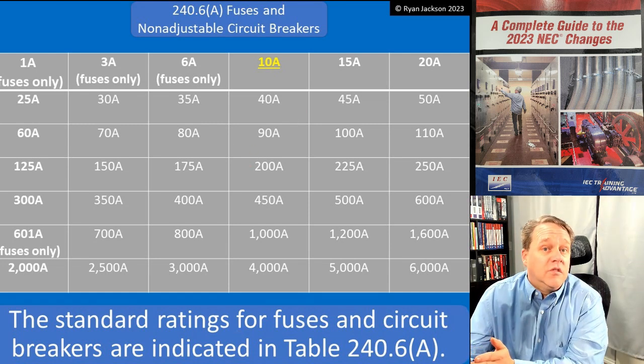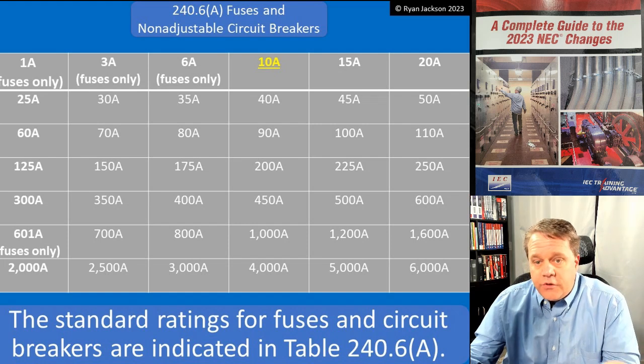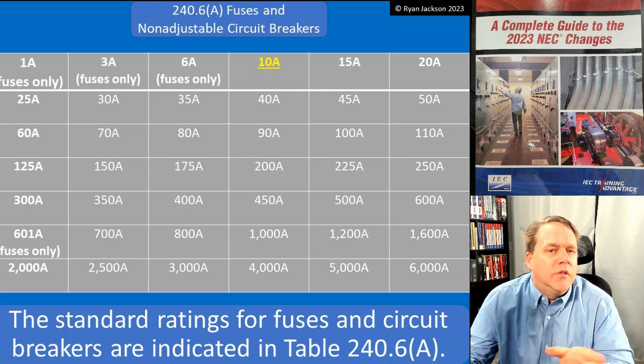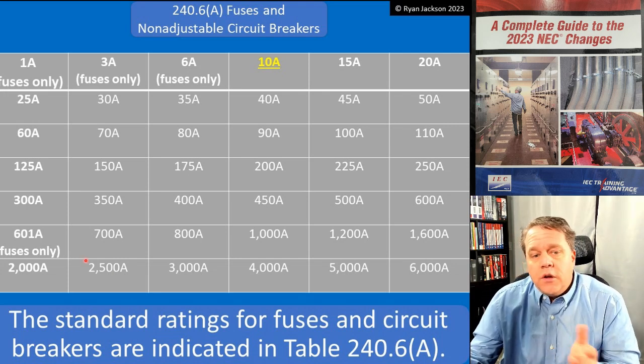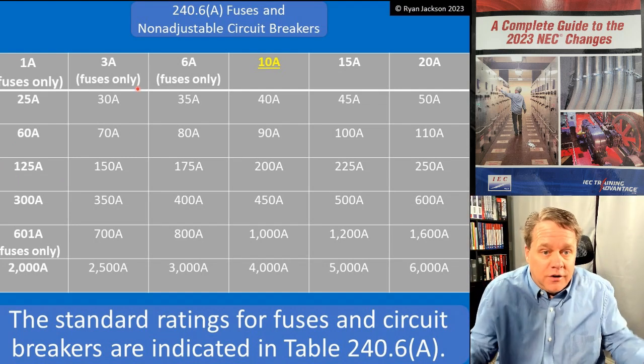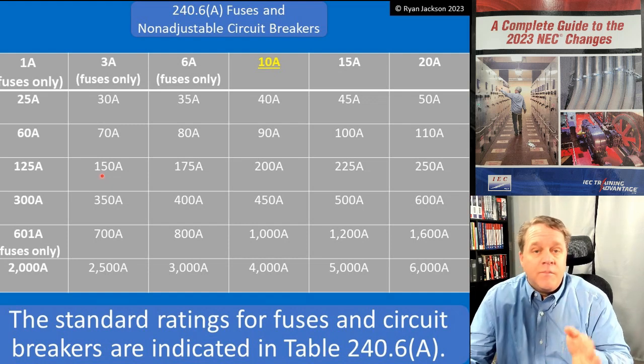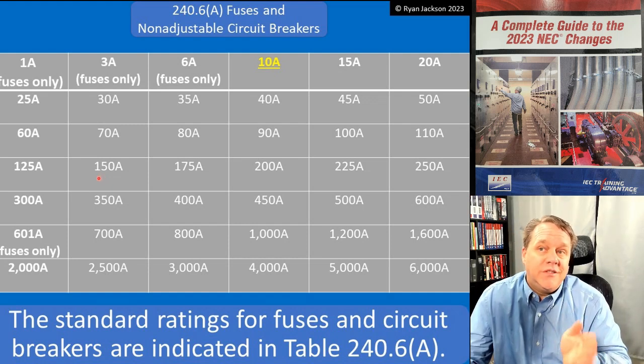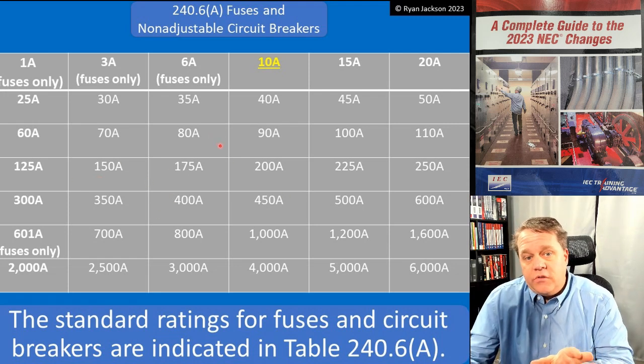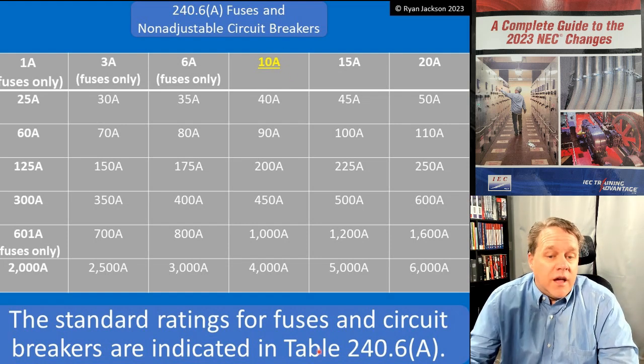This table is really essential when it comes to larger-sized circuit breakers. Let's say you have a wire that's good for 130 amps — I think 1 AWG is good for 130 amps in the 75-degree column. Can you put it on a 125-amp breaker? Sure. Could you put it on a 150-amp breaker? Yes, because 130 amps is not a standard rating. So it's important that we know the standard ratings of fuses and breakers, and 10 amps is now considered a standard rating for breakers.